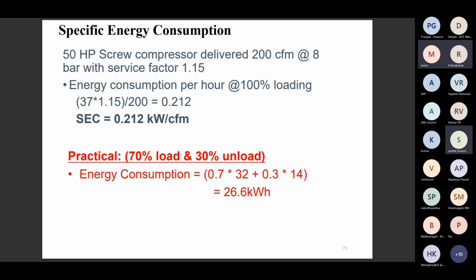Still it is very high. Nowadays, the manufacturer says only 0.16 kilowatt per CFM generation. And practically, at the rate of 70% loading and 30% unloading, the energy consumption is 26.6 kilowatt, and the CFM rating is also less than 120 CFM. So the specific energy consumption is very high, because 26 divided by 120 means the specific energy consumption per CFM is very, very high. Next.